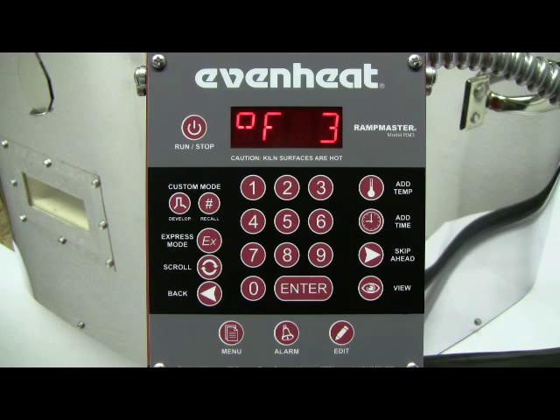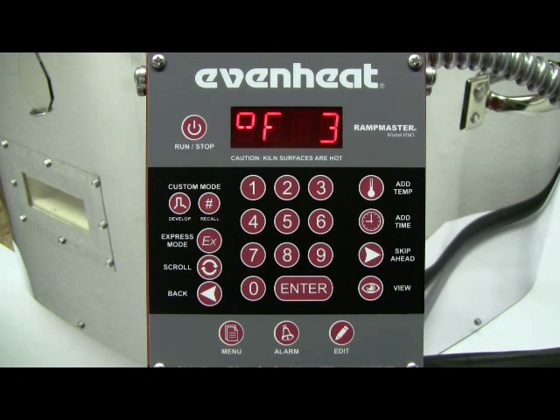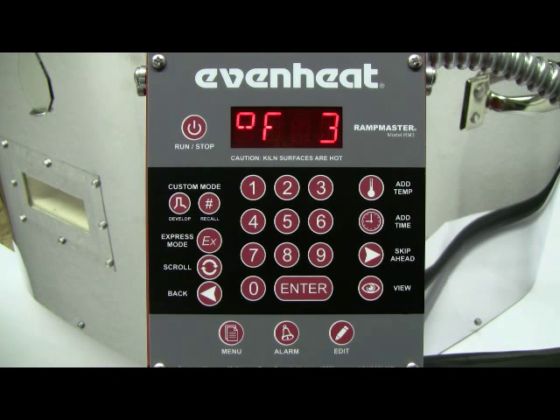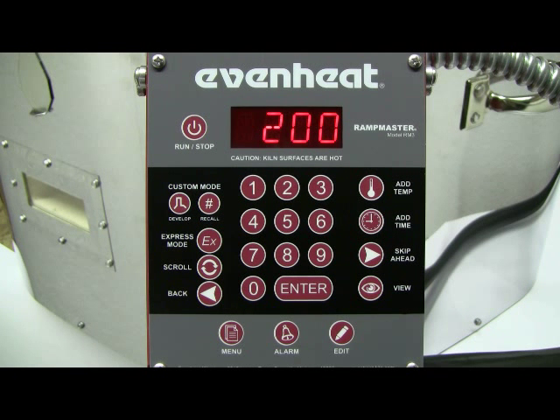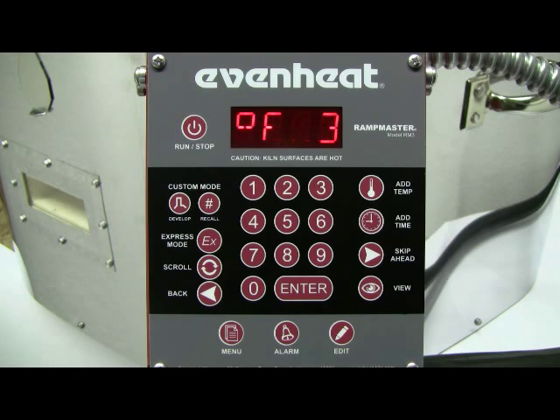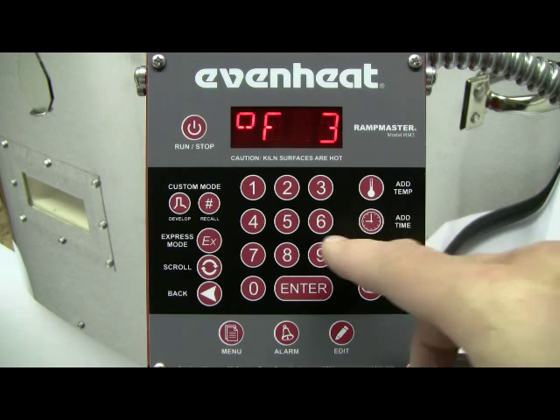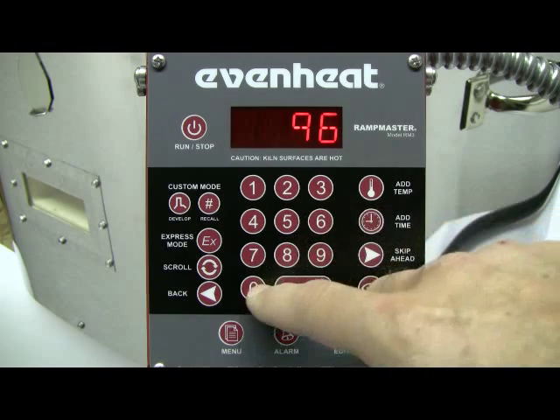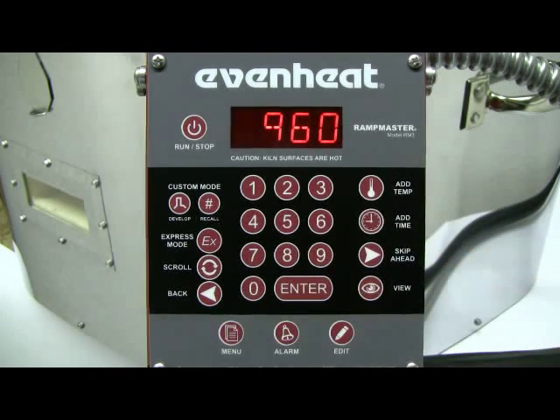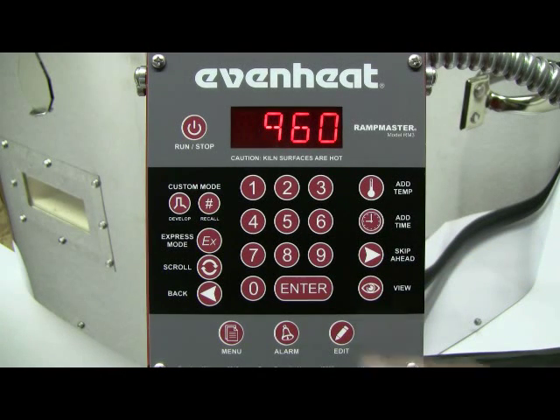The display now reads degrees Fahrenheit 3. The RampMaster is asking for the desired temperature for segment 3. Since this is our annealing temperature, we'll choose 960 degrees. Type in 960, then press the ENTER key to store your choice.